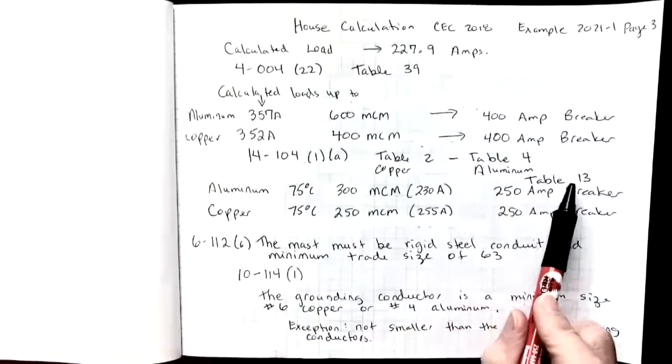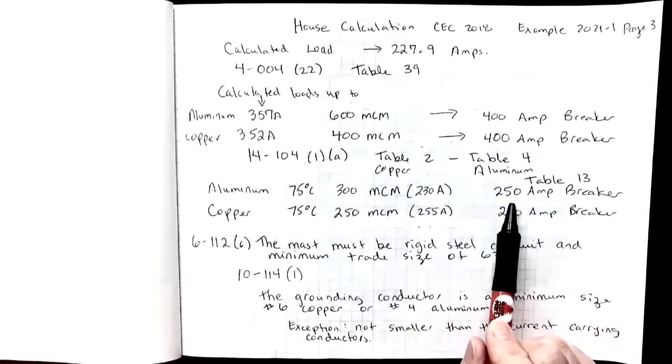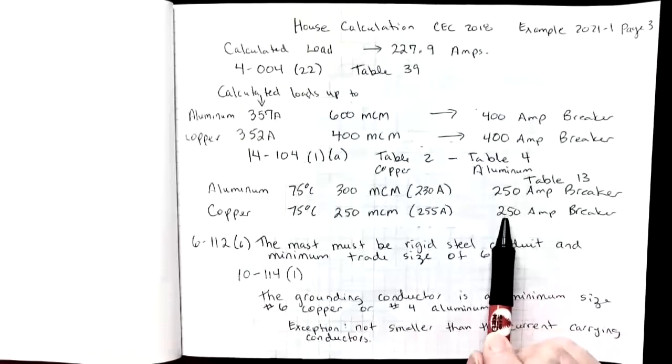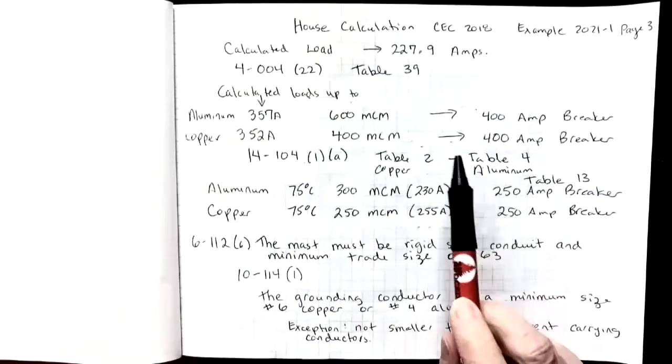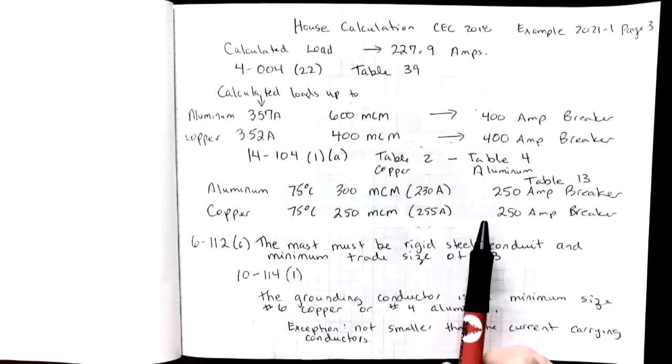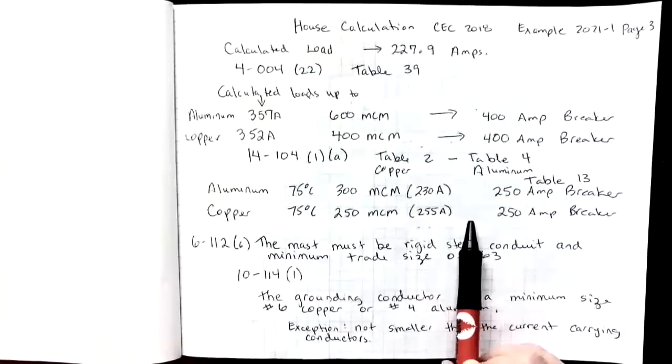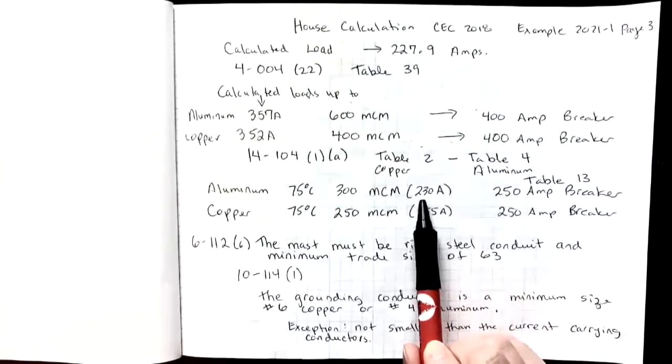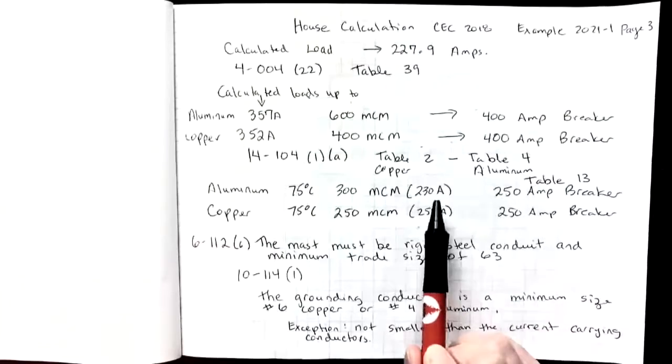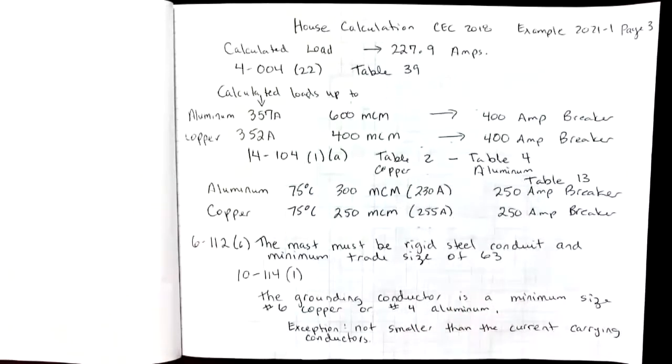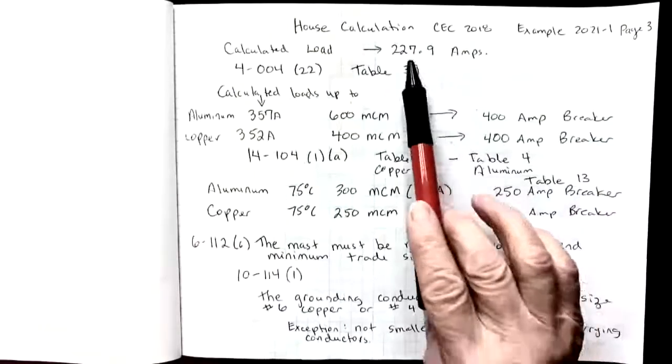Then what I do is I go to table 13, and I see what size breaker I can use on these wire ampacities. And in either case, I'm allowed to use a 250 amp breaker. When I compare what table 39 had to offer to what tables 2, 4, and 13 have to offer, it would be a less expensive installation if I could use a 250 amp breaker and use either copper or aluminum, and it would be a lot cheaper than going with a 400 amp service. And that would be perfectly fine. Still covers my calculated load.